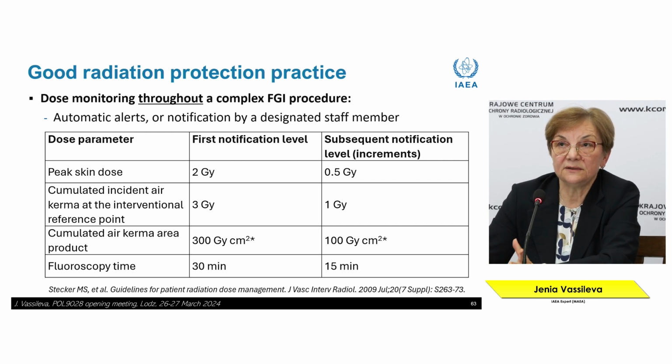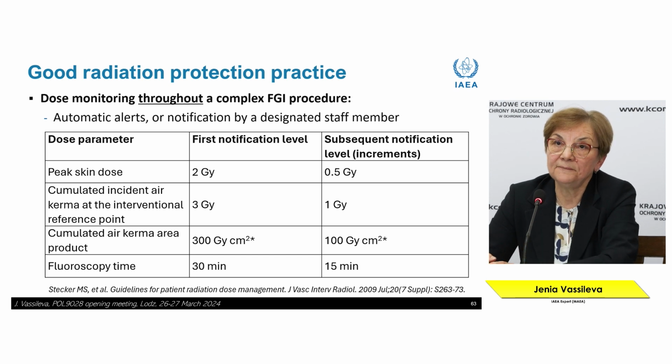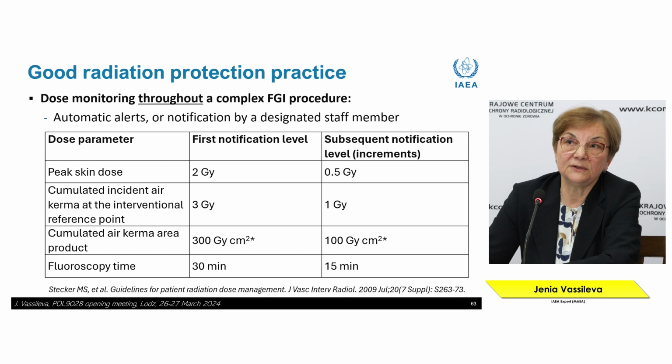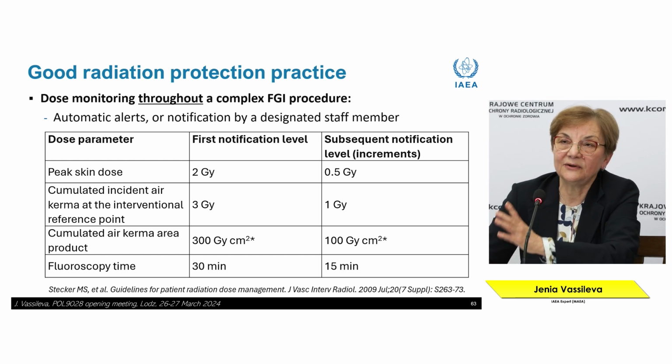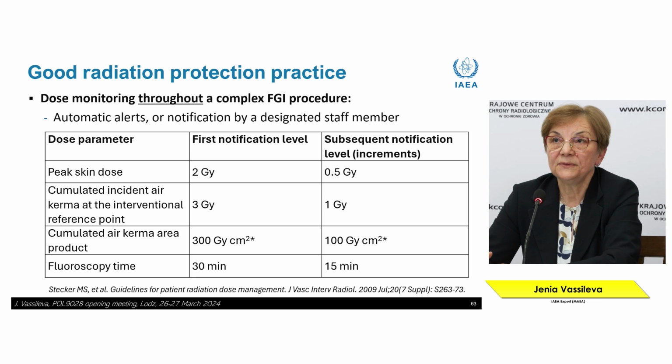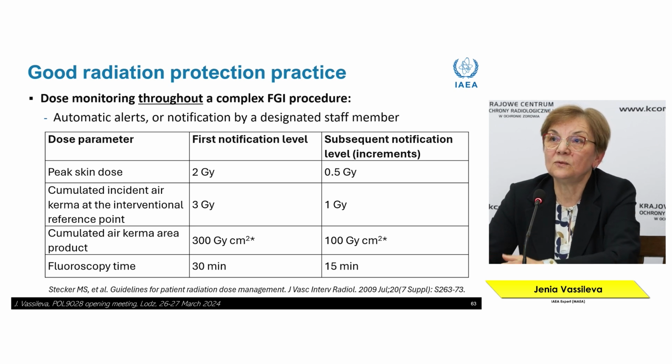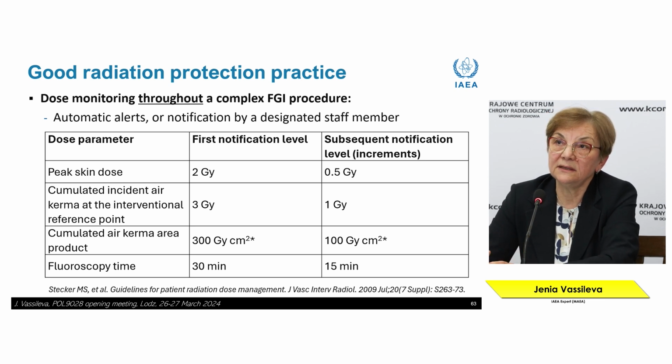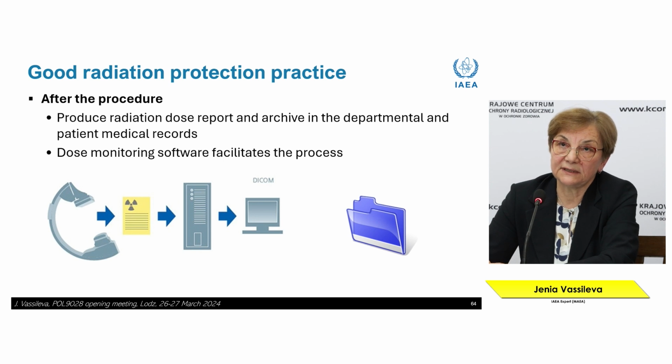As you can see here, if only cumulative incident air kerma is available, when it reaches 3 grays, the first notification is given to the operator, and then with every subsequent 1 gray increment, the next notification. This is very practical to help reduce the risk of skin injury.